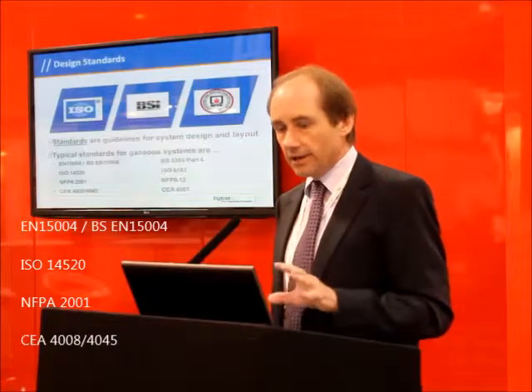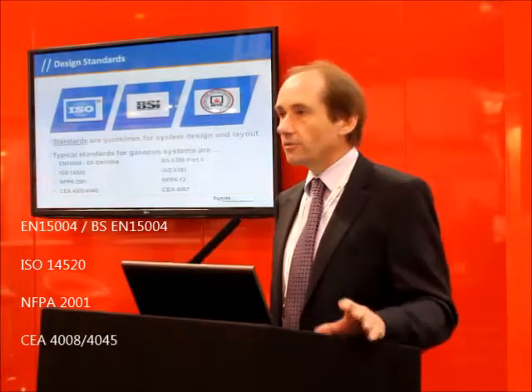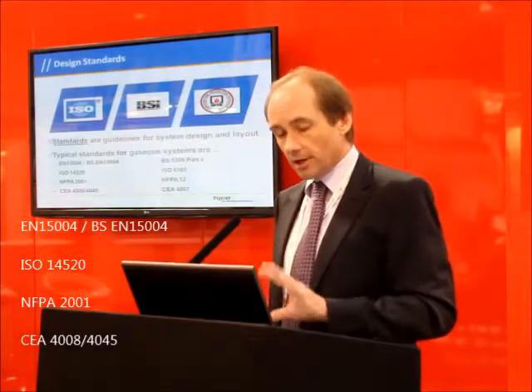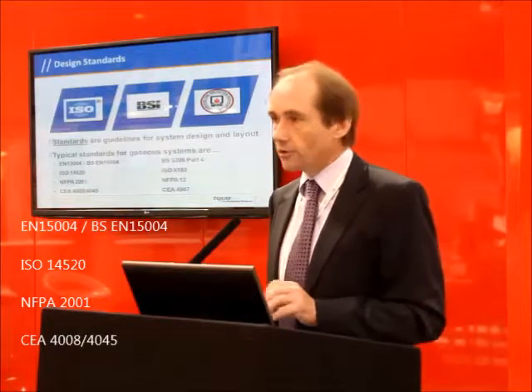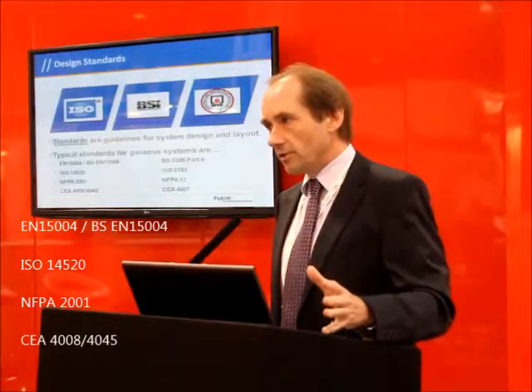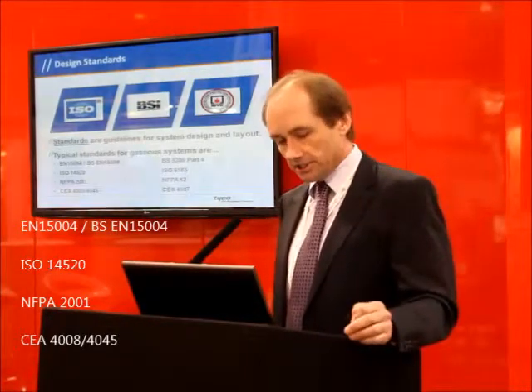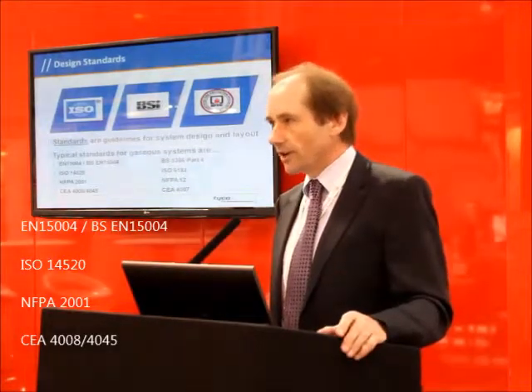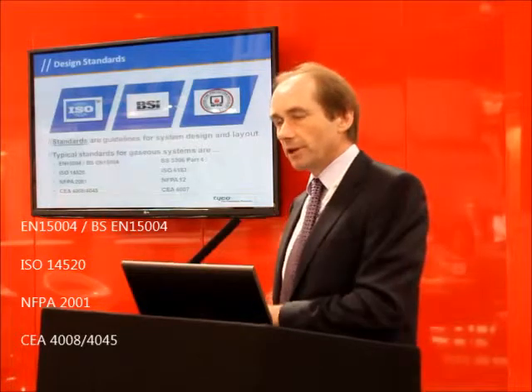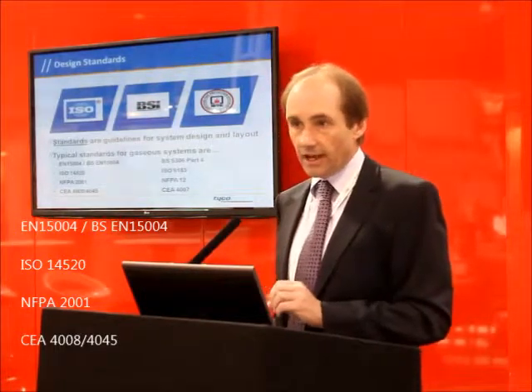The common standard for the UK and Europe is EN 15004, or in the UK BS EN 15004. ISO 14520 is very similar to the European standard but used on an international basis, with certain countries adopting it as their national standard. Probably the most common standard worldwide is NFPA 2001 — the US standard used in the US, most of South America, parts of Asia-Pacific, and the Middle East. There are also the CEA standards written by the Centralised European Insurance Group: CEA 4008 covers inert gases and CEA 4045 covers the halocarbon agents.